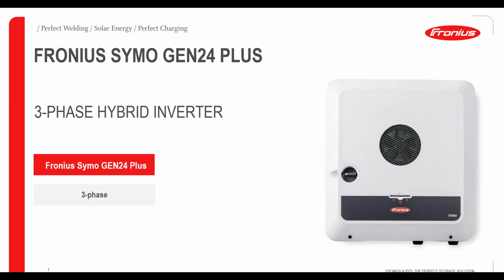Then we have the Symo version, which is a 3-phase hybrid inverter with 2 MPPTs again. The first MPPT is up to 25 amps. So here again, we have the possibility to connect 2 strings up to 25 amps, and on the second MPPT, we have the possibility to connect 1 string up to 12.5 amps. Power class here is from 6 to 10 kilowatts. We are even going to launch our new Symo inverters with lower power class from 3 to 6 kilowatts, which we are going to talk about in more detail in the coming slides. Here again, we have 1 battery connection possibility up to 22 amps.